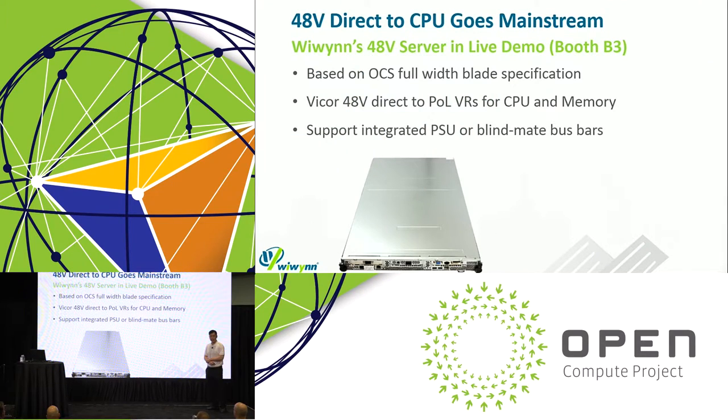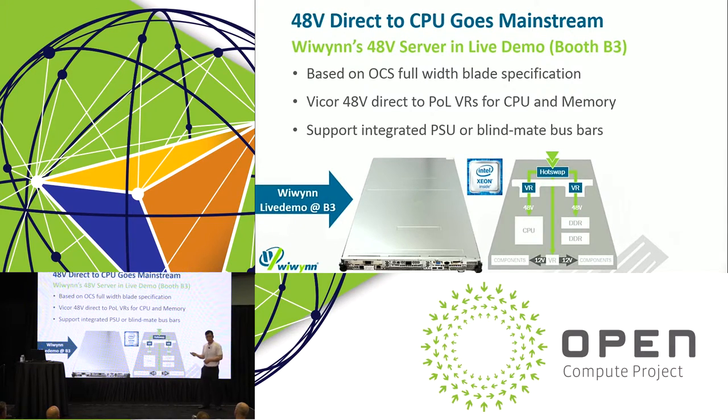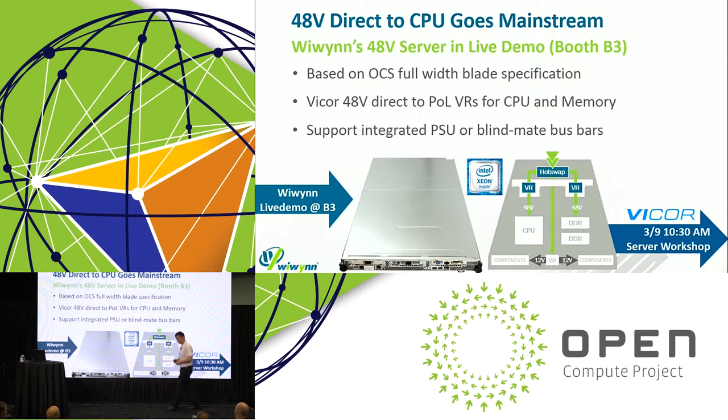Fourthly, Wiwynn has a 48-volt solution, also available as a live demo. It's based on the OCS full-width blade specification, utilizing Vicor 48-volt direct-to-point-of-load voltage regulators for your CPU and memory. It supports integrated PSUs, and to fully leverage power efficiency, it also supports connection to the blind-mate bus bars. We have a live demo at Booth B3, as well as a specific server workshop tomorrow at 10:30 AM — please feel free to drop by.